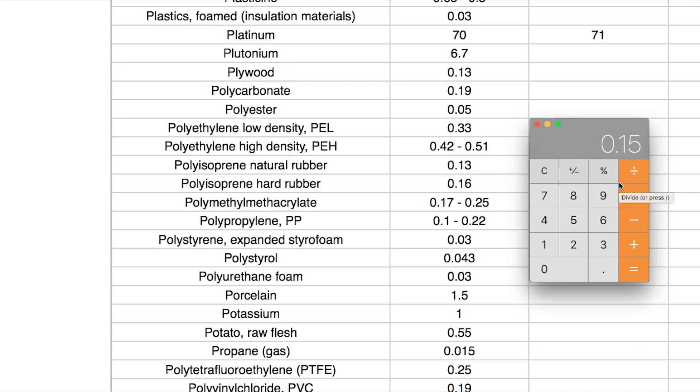What we need to do next is two things really. One, work out the difference, the average and difference in temperature, or for example, a day. Typically in winter, you're looking at about 20 degrees difference from outside to inside. So let's do it on 20 degrees. So we multiply that by 20. That equals this. Now we need three watts per square meter. This is our square meter wattage through a 200 millimeter thick polystyrene. So all you need then is the surface area of your building. I know that the surface area of the upper part of the dome is 70 square meters. So we multiply that by 70 and that comes out at about 210 watts. So I would need an electric heater of about 210 watts to heat the inside of the dome to 20 degrees above outside temperature.